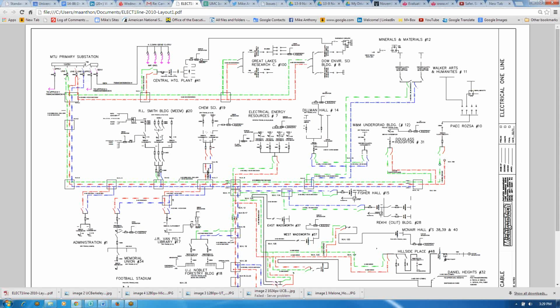So what I'm seeing up there is about 8.8 megawatts of generation? Yes. And is that the average or peak load for you? No, the load in winter is actually around 5, maybe 5.5, but we keep at least one extra generator in case another goes down. So the entire campus is supplied at 5.5 megawatts? Yes.